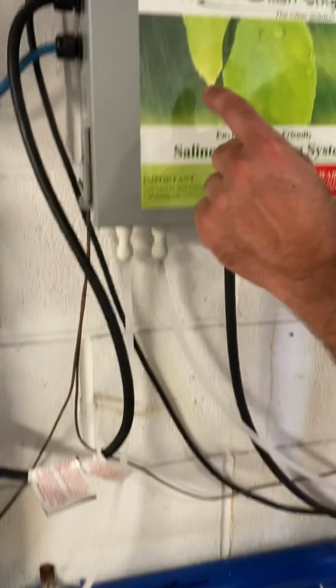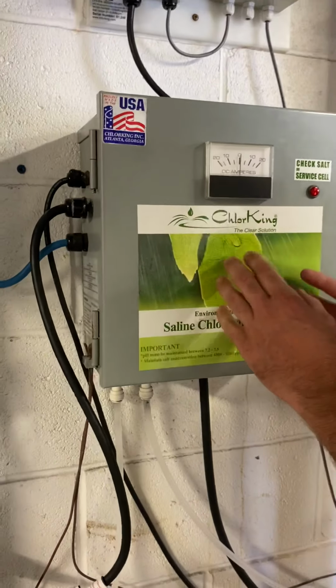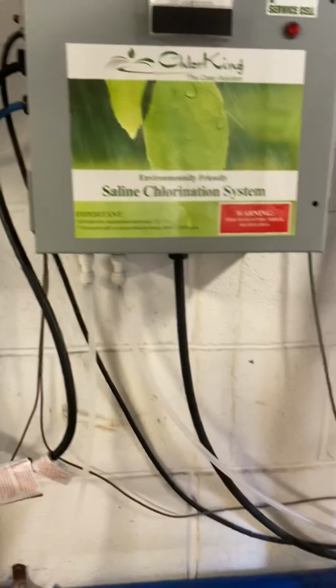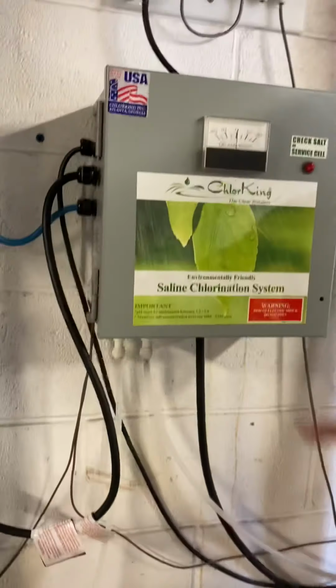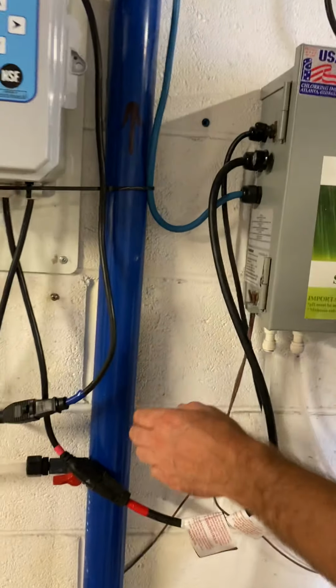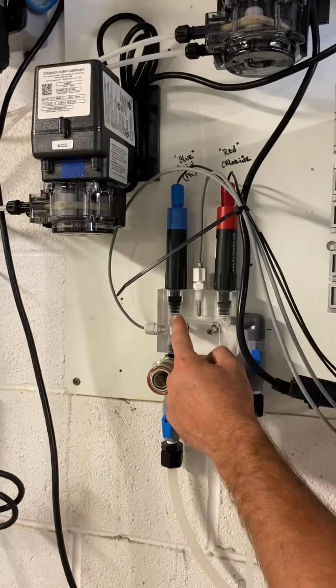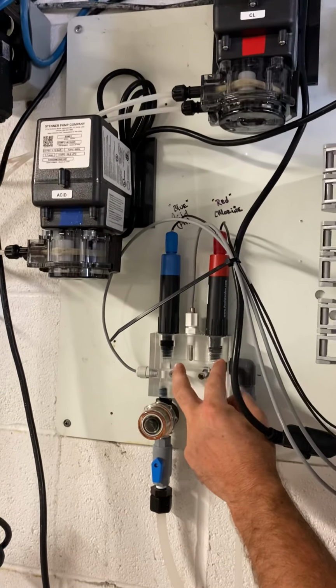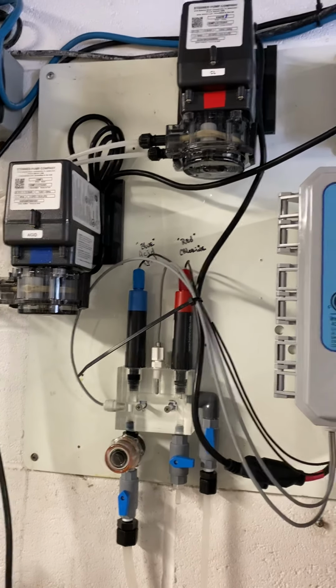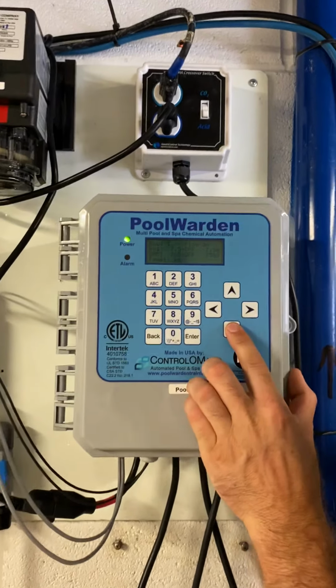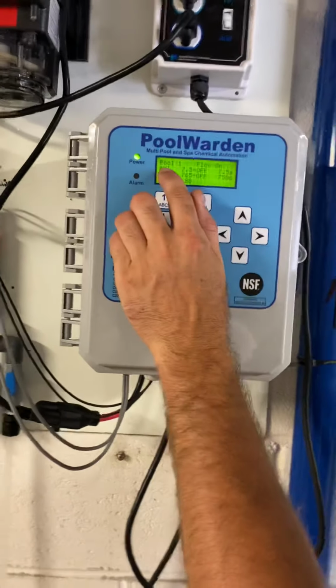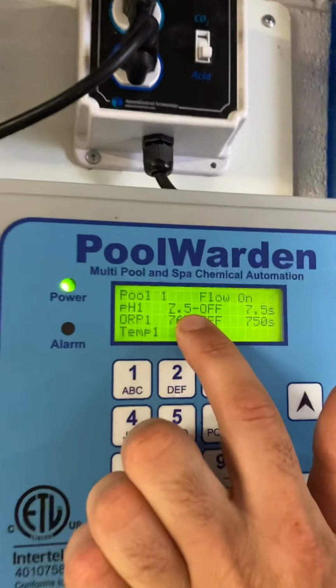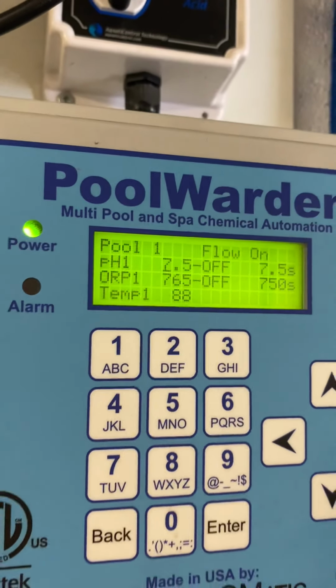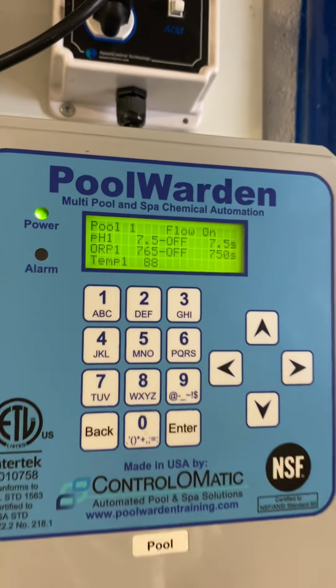And this one does it a little different, where the sample actually goes into the salt system because it has to cool components, and then it comes out here and sends it right back into the system. So it's doing a full loop. All it's doing is taking a sample from the pool and sending it back into the pool. These probes are reading the pH and the chlorine, and it sends a signal into the controller. This controller, you press a button to light it up. There's your pH. That number right there, that 7.5, is the actual reading that blue probe is taking and sending to here.